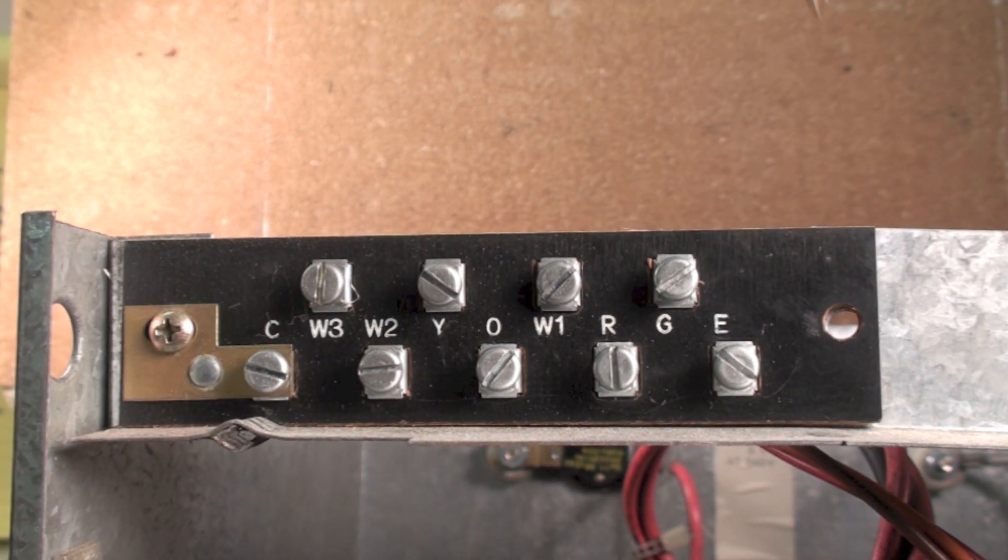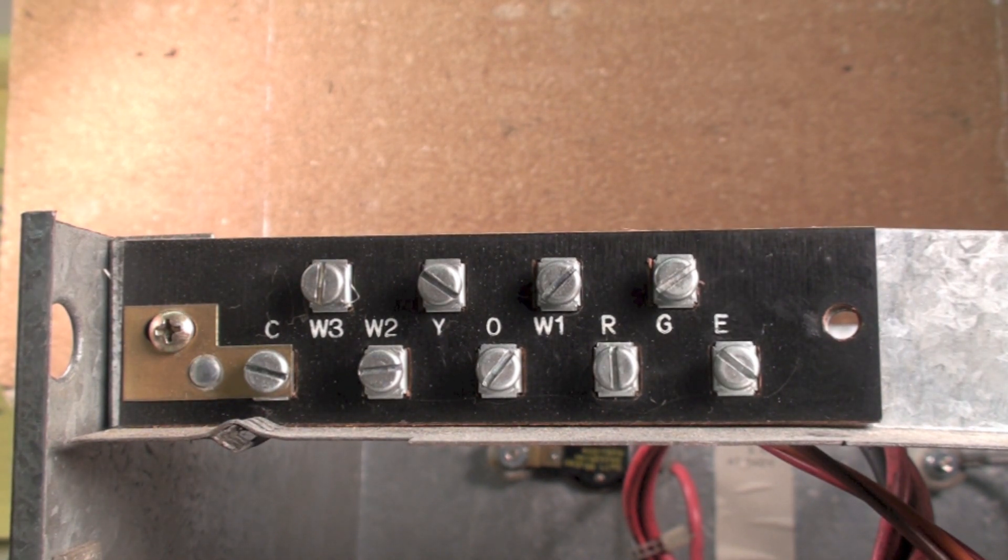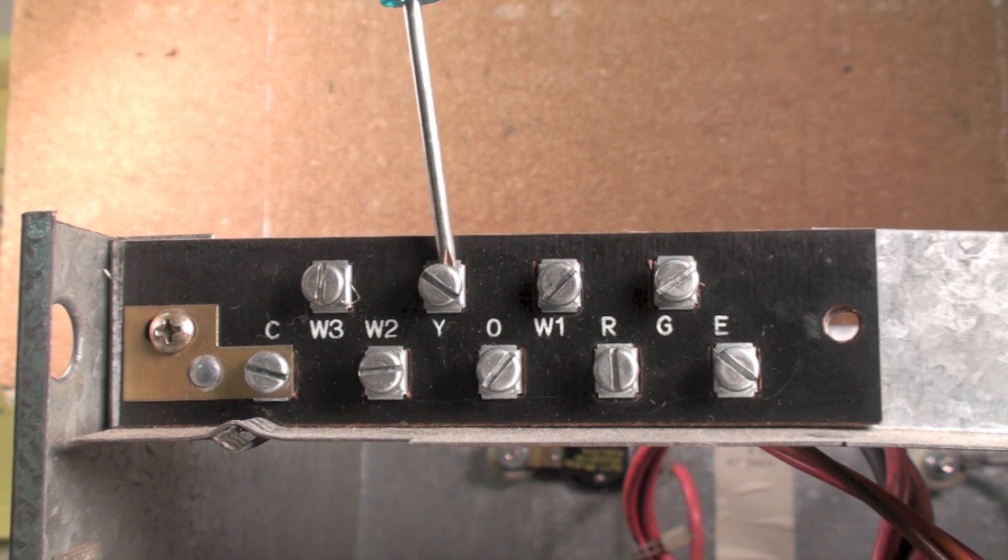E is for emergency heat. Usually what happens is if E gets power, it locks out the outdoor unit. In other words, it drops Y out, doesn't go to Y.